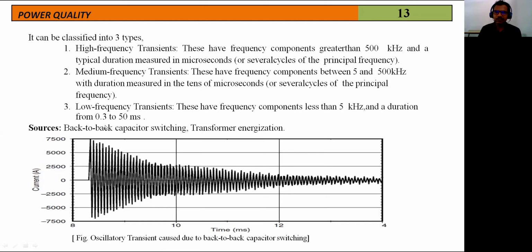One of the waveforms for oscillatory transients is shown in the figure. This figure shows an oscillatory transient caused due to back-to-back capacitor switching. You can see here, this is the actual current, just starting from 0. The actual current will be very small, in amperes. But whenever the capacitor bank is switched suddenly, oscillations come in the positive way as well as in the negative way. You can see here approximately 7,500 amperes going in the positive as well as negative directions.